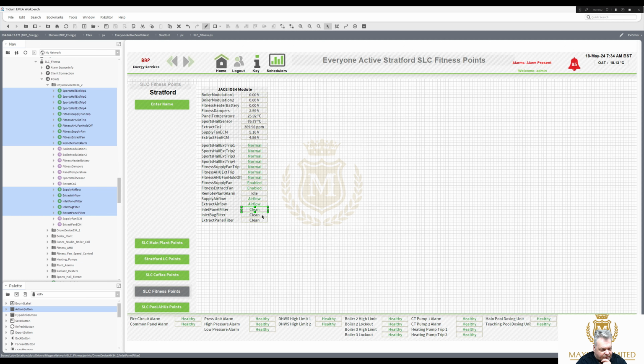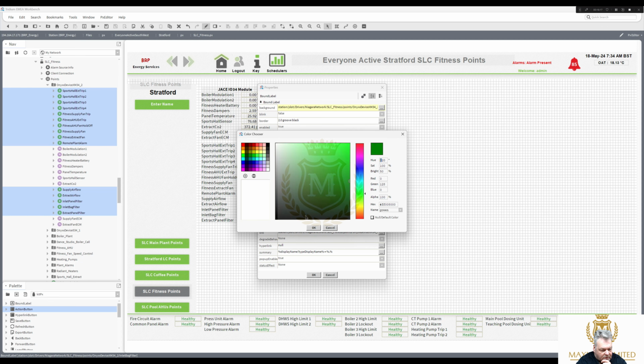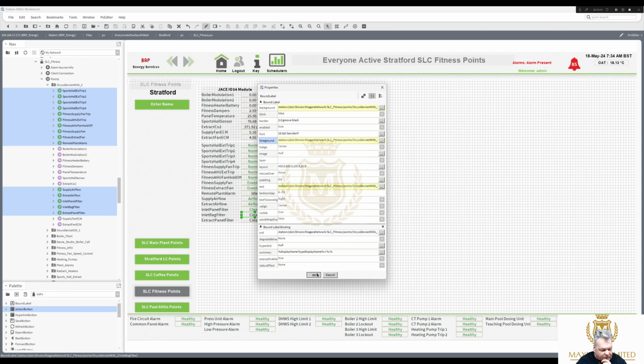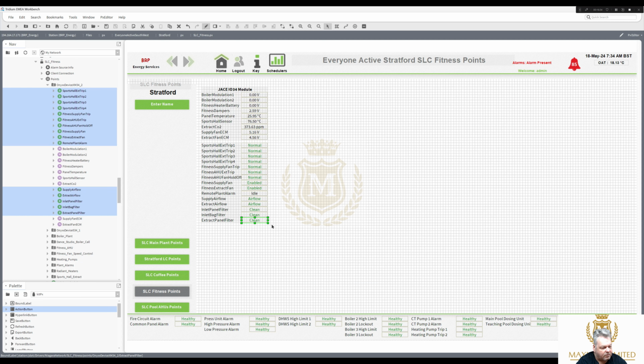So that's the filter is clean and the pressure across it is clean. It's not a high pressure, or it's not a low pressure. All it is is a pressure switch across the filter. Just turns on and off. And it's got a dial that you set for your pascals or your pressure. Right, so that's that done for that I/O module.